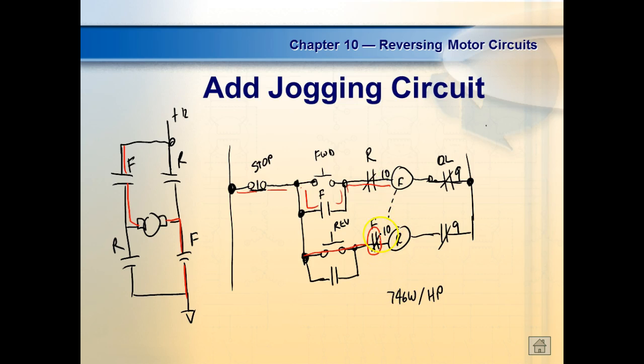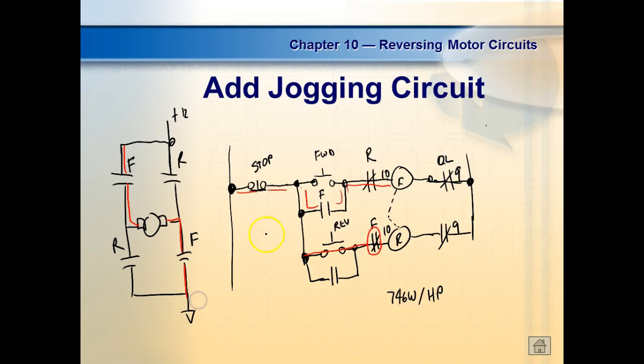Follow me so far? Now I need a normally open contact. I can't use the one that's connected over here, right? You understand? Because that would bypass my interlock. So what contact would I use? Okay. So I need a normally open contact. Here's a normally open contact. Can y'all see the number? 5 and 6. So this would be 5 and 6, or 6 and 5, whichever way you want to wire it.